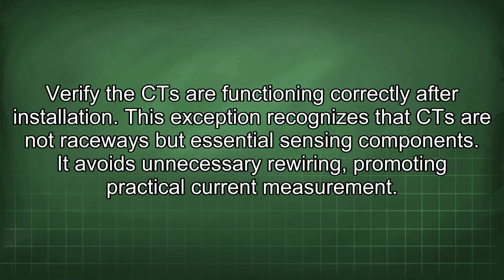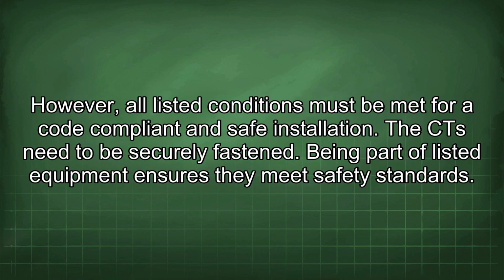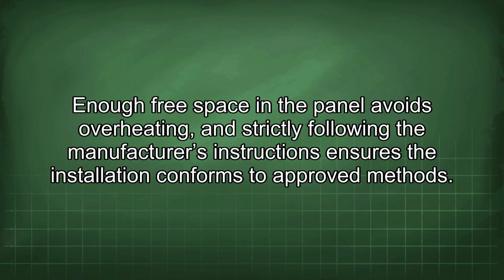This exception recognizes that CT are not raceways but essential sensing components. It avoids unnecessary rewiring, promoting practical current measurement. However, all listed conditions must be met for a code-compliant and safe installation. The CT need to be securely fastened. Being part of listed equipment ensures they meet safety standards.